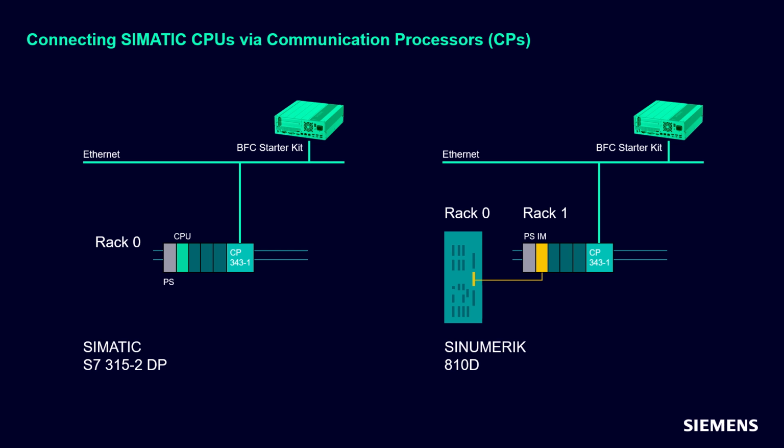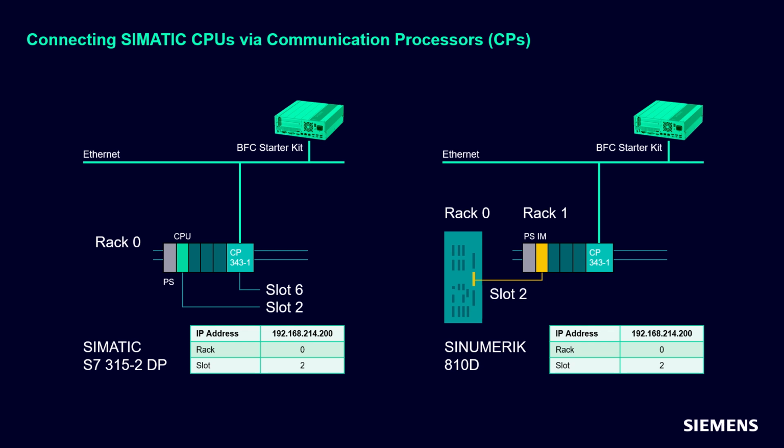At first, there is the rack slot addressing. CPUs, at least the first S7-300s, used a very strict rack slot addressing. In most cases, the CPU was located at rack 0 and slot 2. Even if the Ethernet connection was done using a CP343-1, which might be on rack 0 slot 6, you need to use the rack and slot from the CPU.